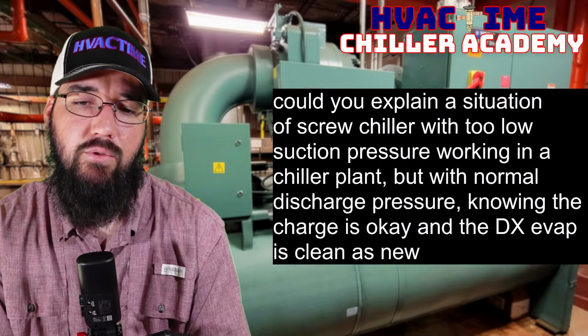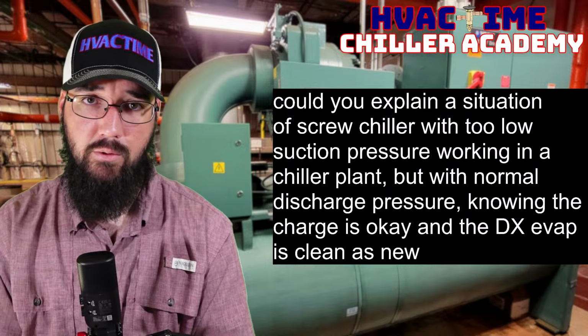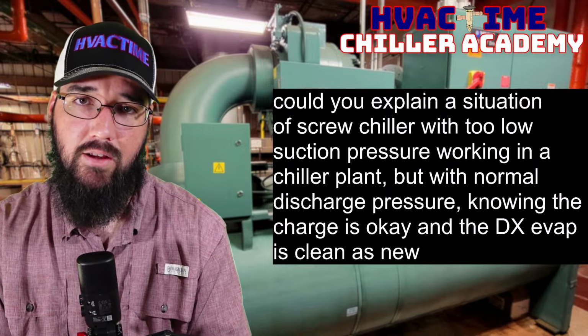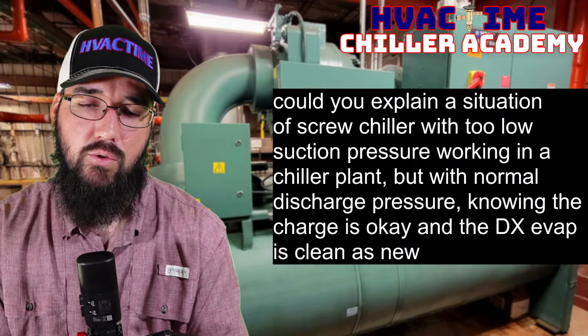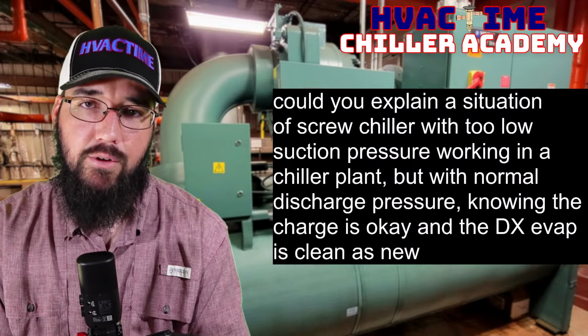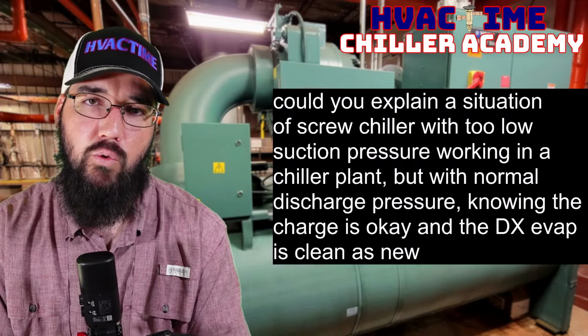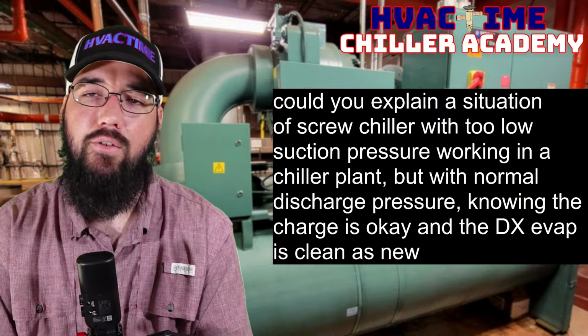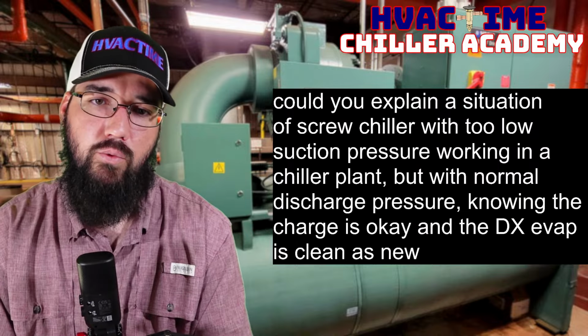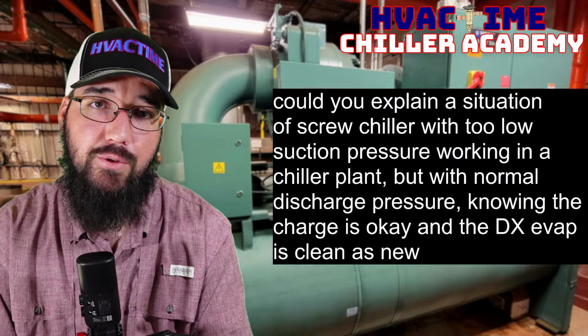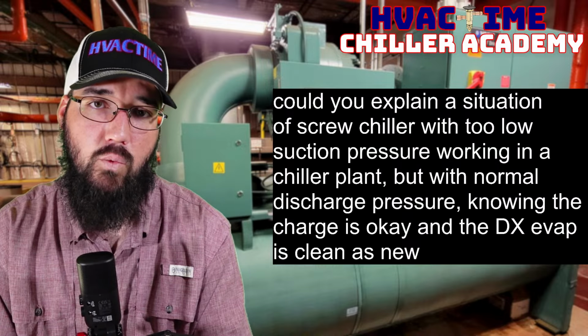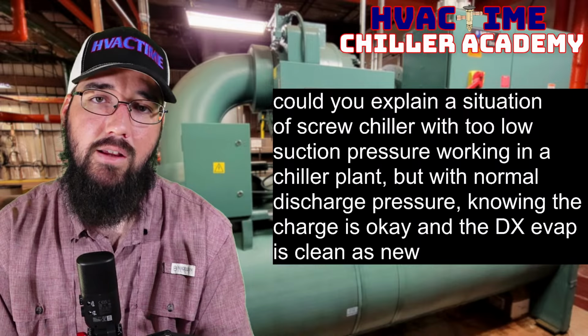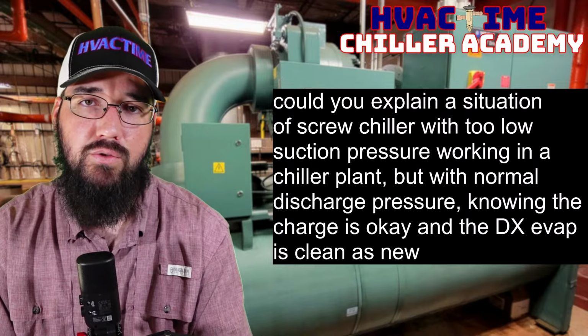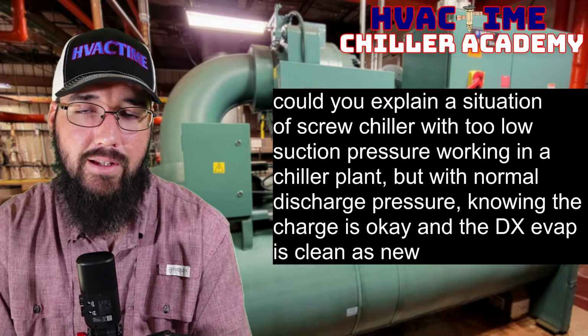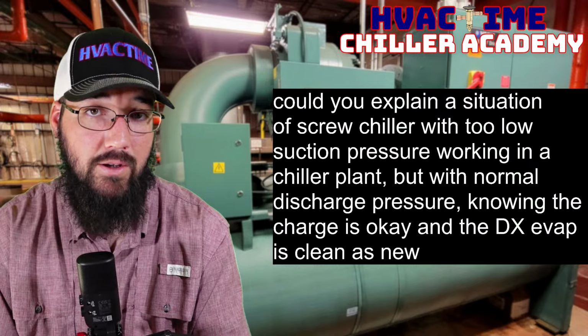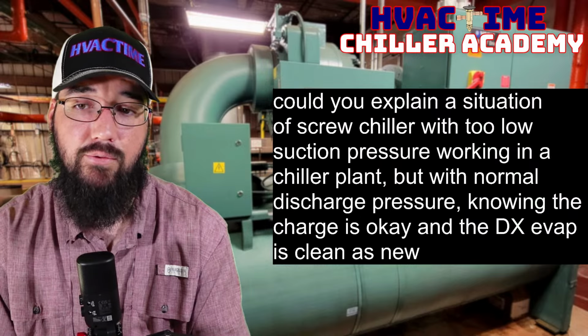And if you have a DX evaporator, I'm going to immediately assume you have a shell and tube DX, which means that even if it's a braze plate, either way, you have a higher approach than you would normally see with a flooded style of evaporator. With a DX style evaporator, where the refrigerant is in the tubes and the water is on the outside of the tubes, it's very normal to see approach values of 8 to 10 degrees. It's very normal, especially with a full load on the machine.